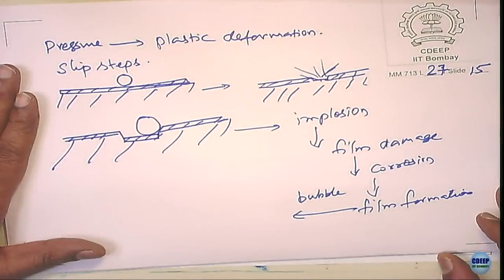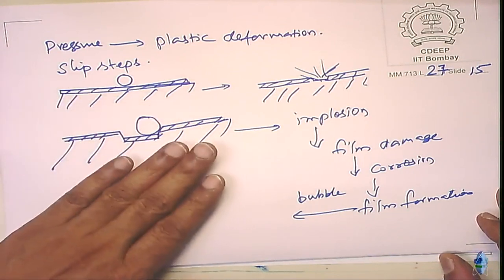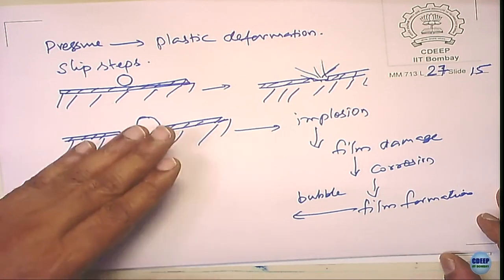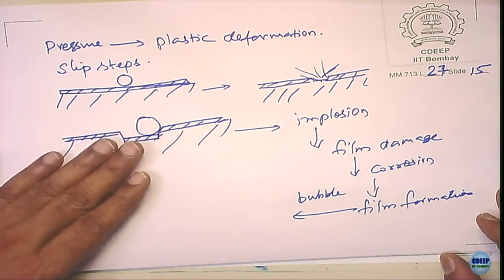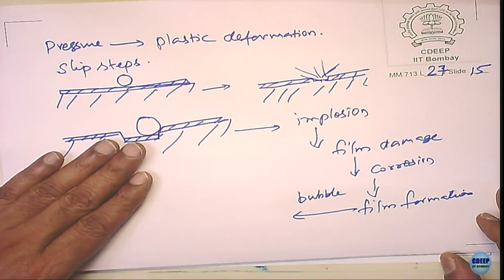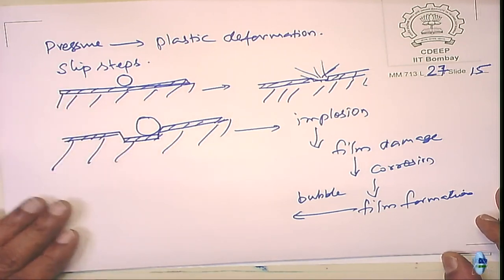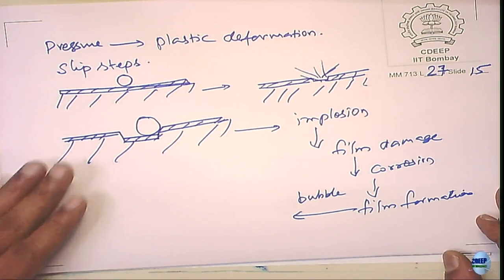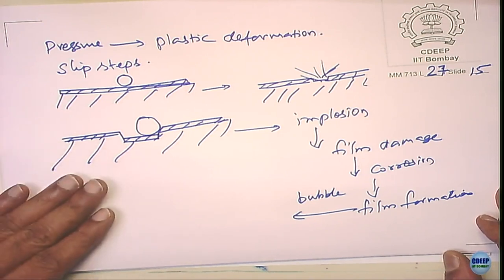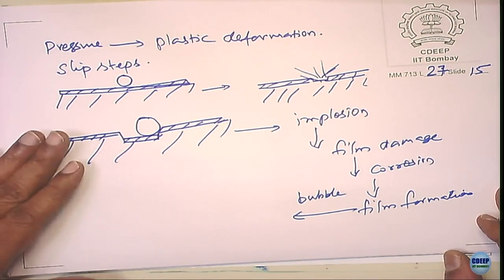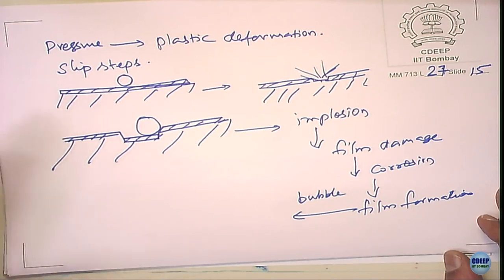So the cavitation damage occurring here is more of a mechanical damage. Corrosion is a consequence of the removal of the film, exposing the bare metal. Further damage then comes by a mechanical process, the implosion of the bubbles. Of course corrosion occurs because the environment interacts and forms the film, and so on.